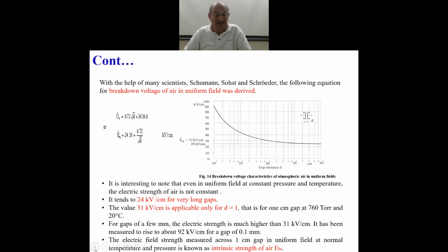As for what Paschen derived, we have learned in the last lecture once again. Many scientists, for example Schumann, Sohst, Schroeder, derived an analytical equation for breakdown of air in uniform field. This was also verified for weakly non-uniform field, as you will see. The equation works out to be that UB peak, as you see here, is equal to 6.72 root of PD plus 24.36 multiplied by PD, in kV.